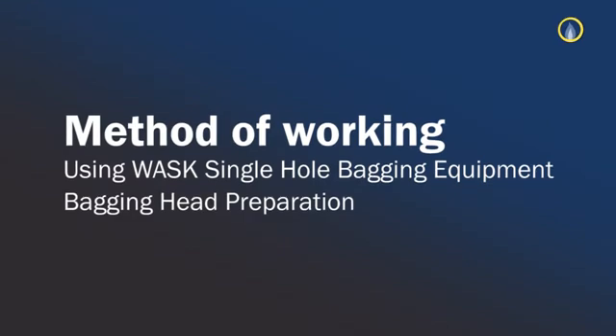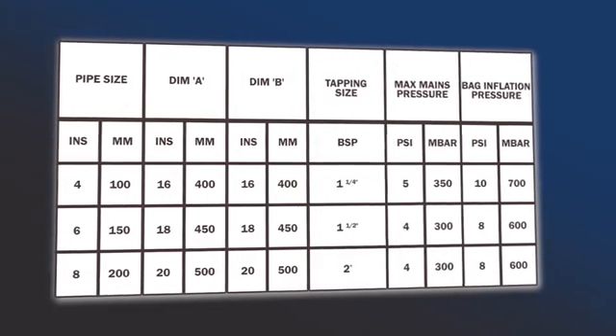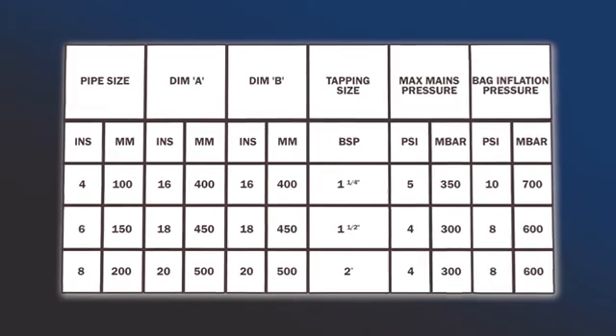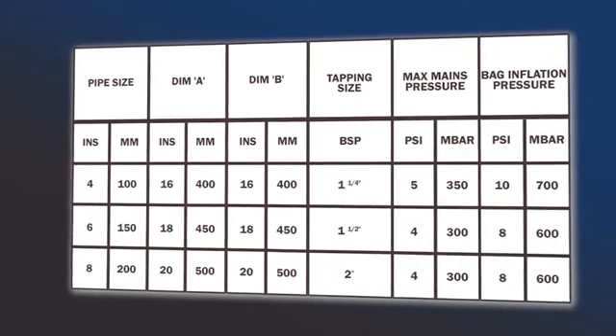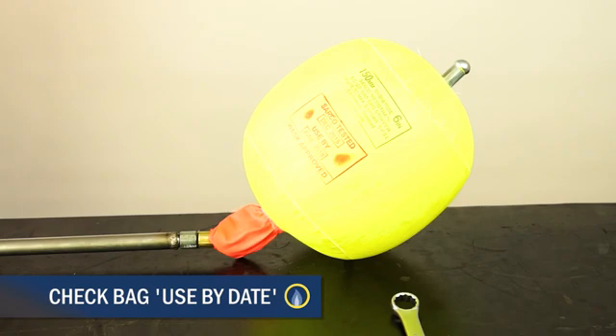Method of working using WASK Single Hole Bagging Equipment. Select the correct size of bag for your main size. You'll require five bags for setting up a two-way stop. Ensure that the O-ring is present in the bag connector and is located in the bottom of the thread. At this stage, check the bag used-by date and general condition.